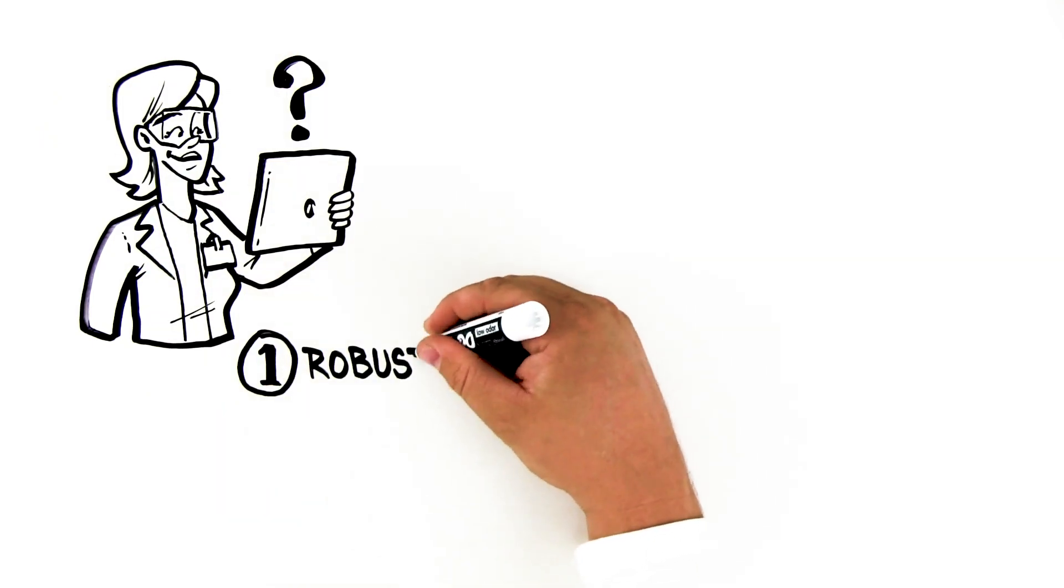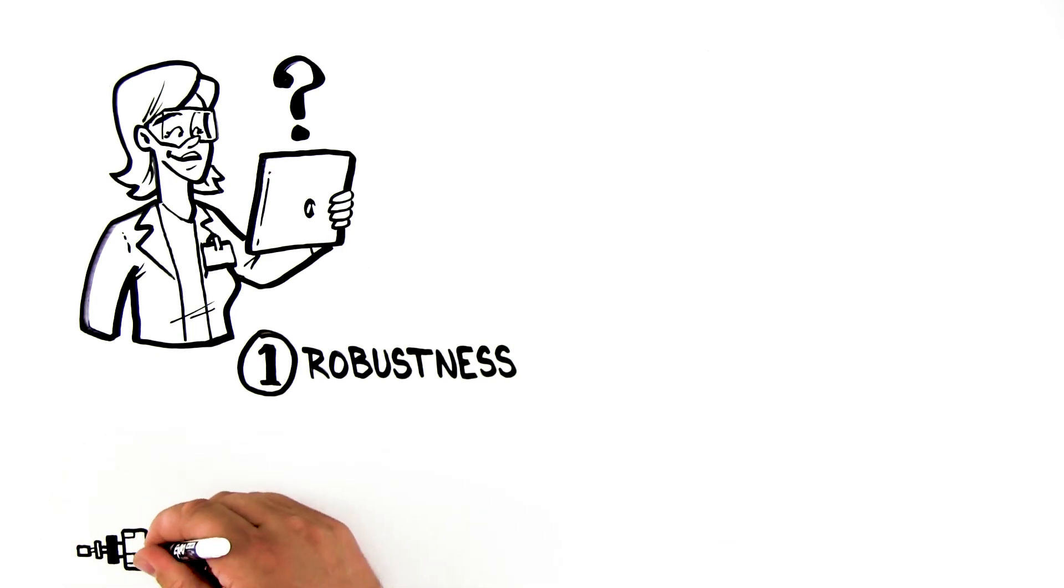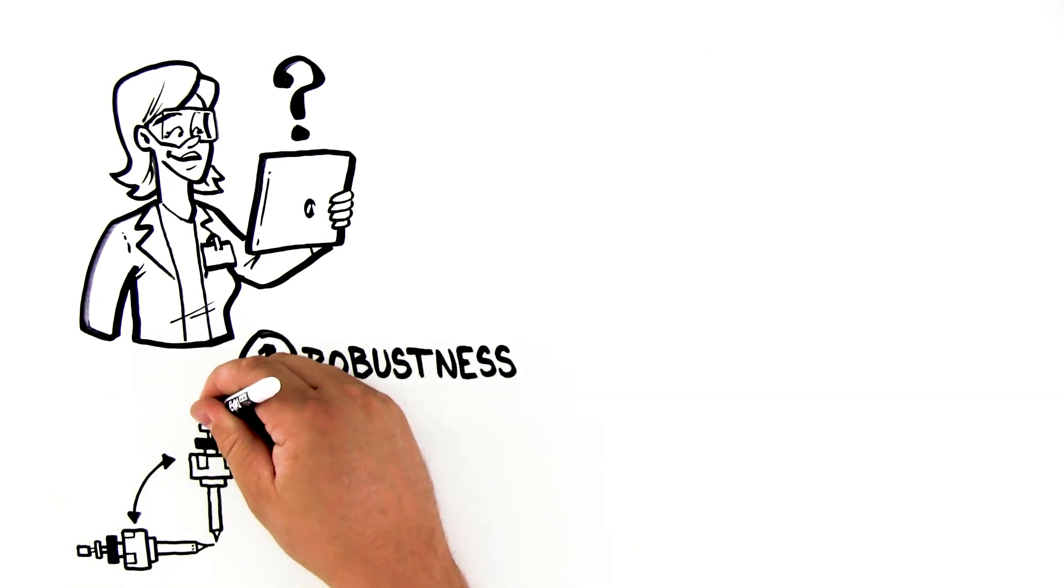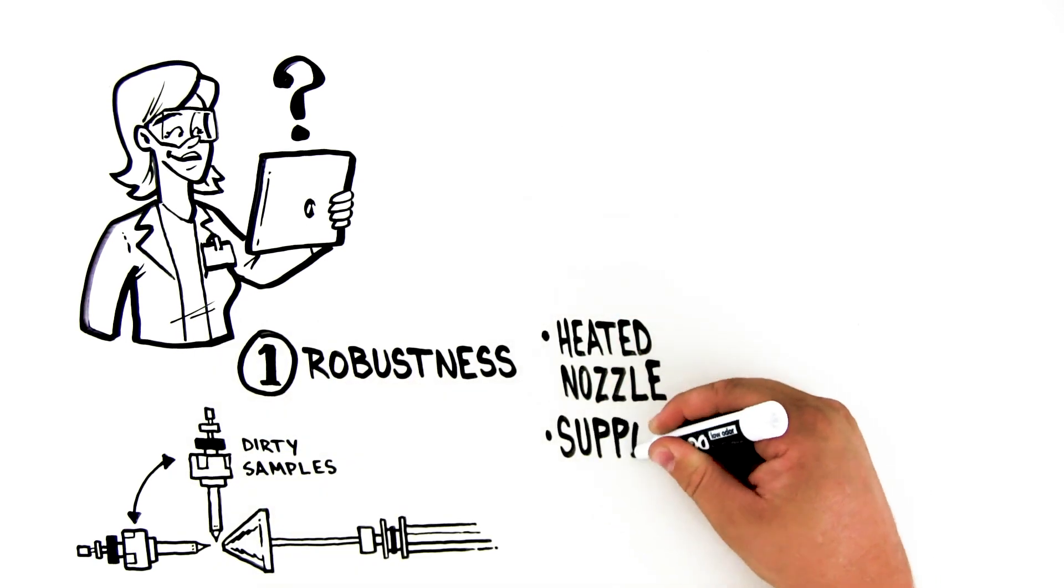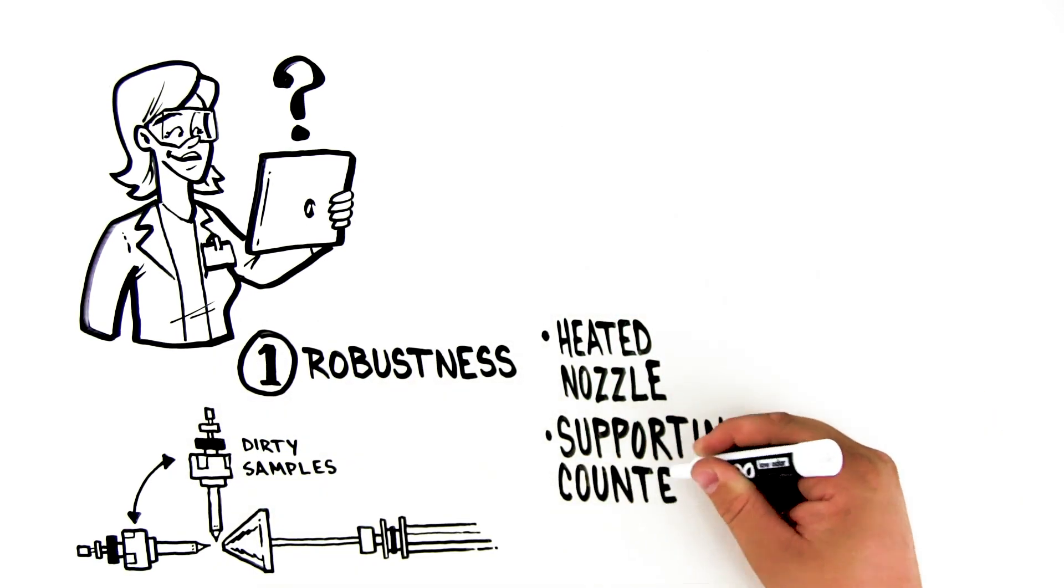First, Jenny considers robustness. An ion source that is orthogonal to the ion transfer tube more efficiently handles dirty samples. A heated nozzle and supporting and counter gas flows further benefit robustness.